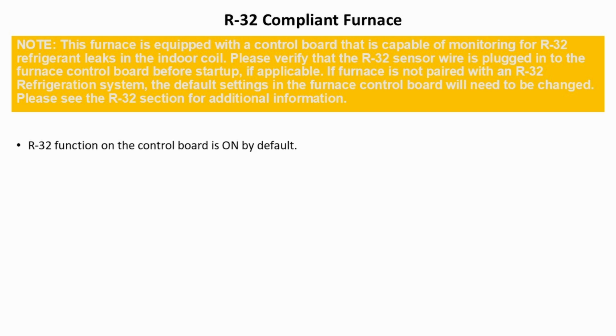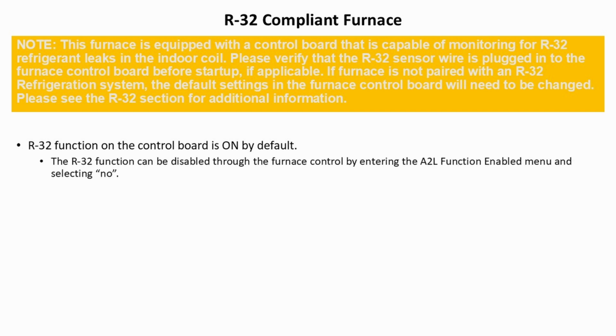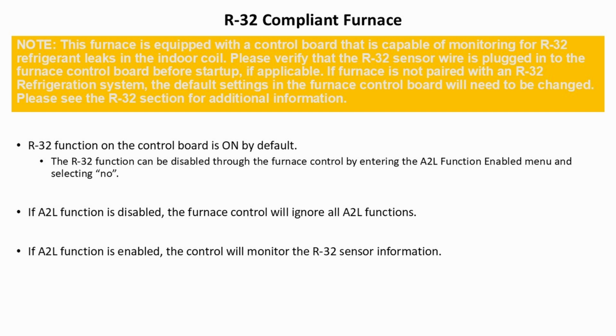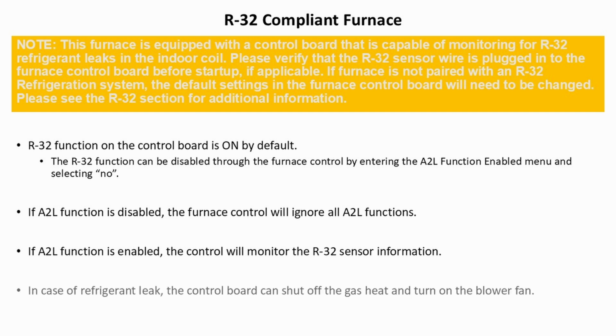The R32 function on the control board is on by default. The R32 function can be disabled through the furnace control by entering the A2L function-enabled menu and selecting No. If the A2L function is disabled, the furnace control will ignore all A2L functions. If the A2L function is enabled, the control will monitor the R32 sensor information. In the case of a refrigerant leak, the control board can shut off the gas heat and turn on the blower fan to dilute the R32 concentration.